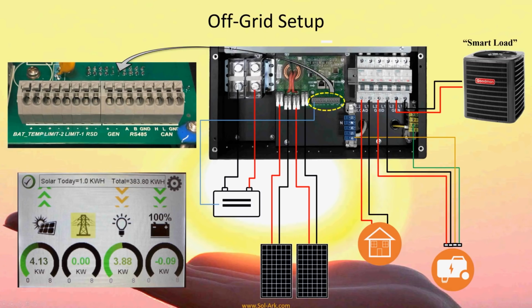All right, so in terms of an off-grid setup, we would actually put the generator into the grid input. We're not normally running the grid or the generator, so we're going to have a yellow icon here. We would also use this gen start connection - this is normally open, and it closes this relay when we need to start the generator.